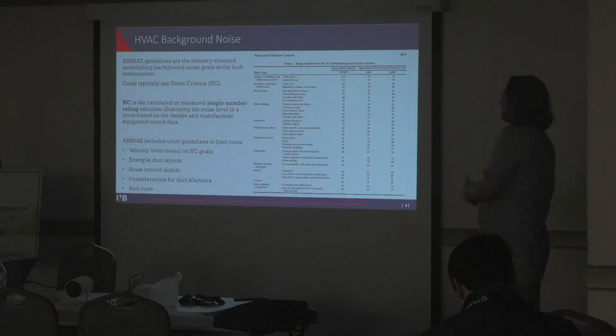Where does the HVAC background noise criteria come from? ASHRAE guidelines are the industry standard that establish noise goals in the built environment. As I said before, in America the noise goals are typically expressed as NC, noise criteria, a calculated or measured single-number rating that illustrates noise levels based on the design of the equipment and the room.